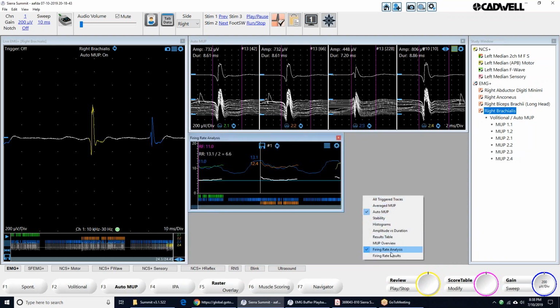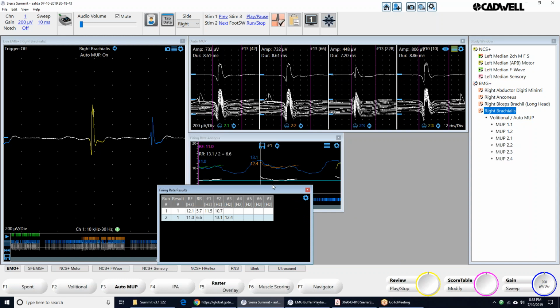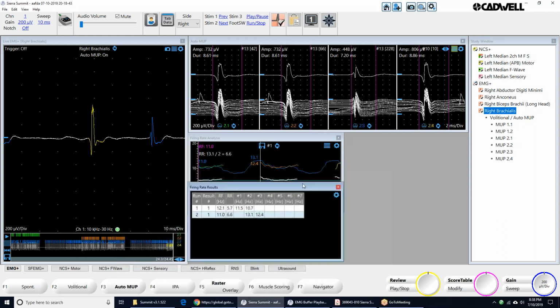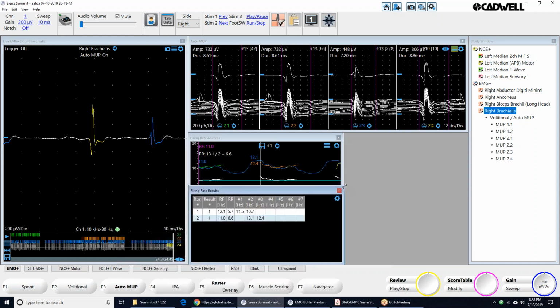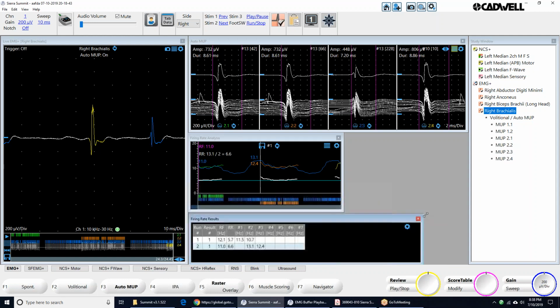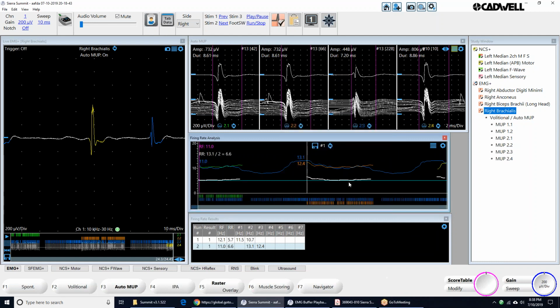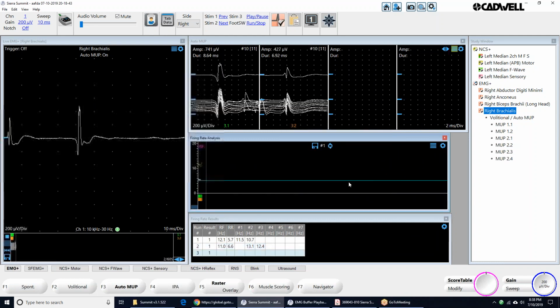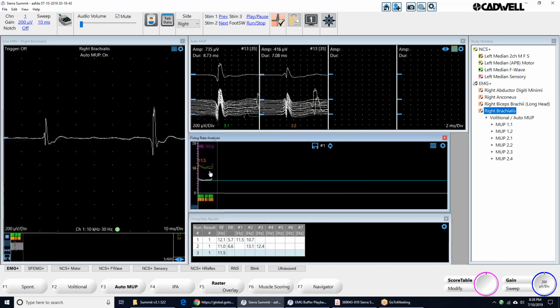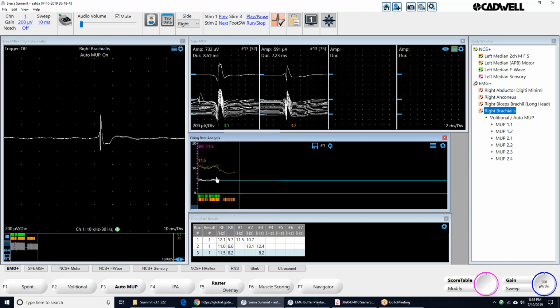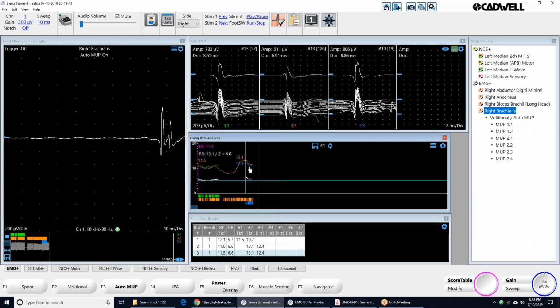And there's also firing rate results. So this allows the user to see some live recruitment ratio information. So what we're doing here is when you're running, you'll see the motor units that are firing, and then we're doing a recruitment ratio calculation. So this white line is the recruitment ratio. So here we have 1 motor unit firing, and then the second motor unit's going to come in, which drops down the firing rate, and we start calculating the recruitment ratio.